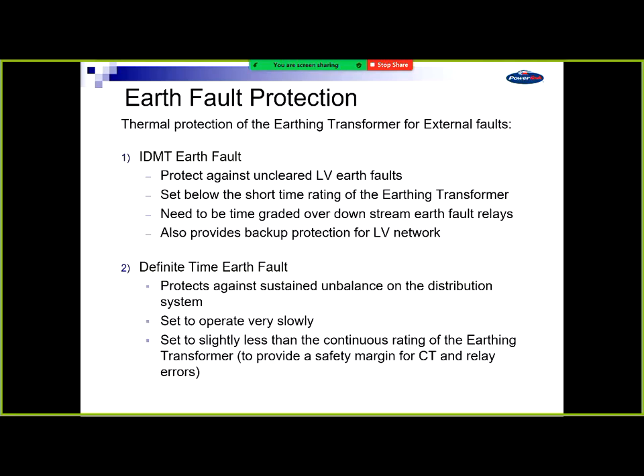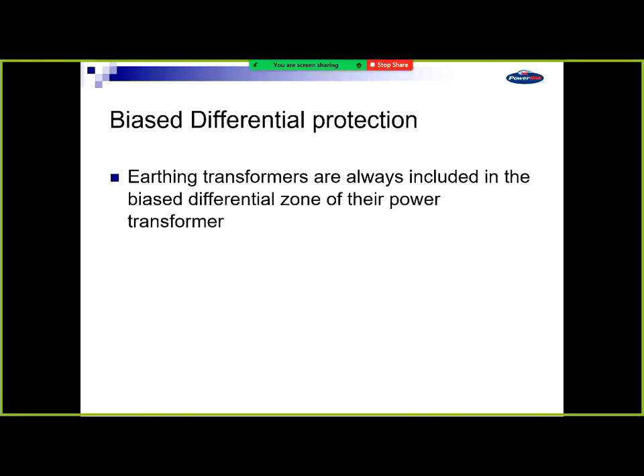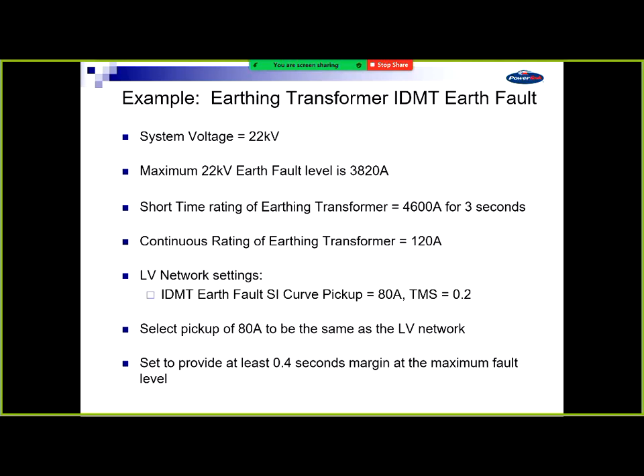The definite time is more around, we know the continuous rating of the transformer, we set below that, and we operate quite slow. So it's not in protection operation time. We've got the example to say that if there's a low voltage fault or an unbalance in their network that's hanging on for a very long time, we trip the transformer. They're always inside the bias differential range, so we're not really worried about a high-speed operation for a low-voltage terminal fault. The bias diff will detect that and operate. So we're not after high-speed operation out of this. So it's the grading with the LV network.